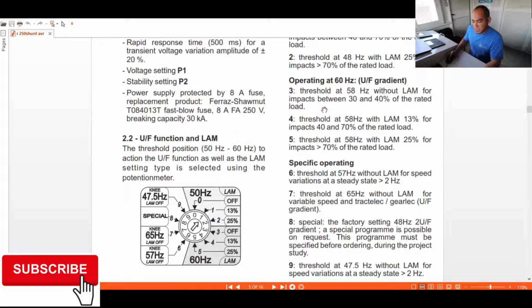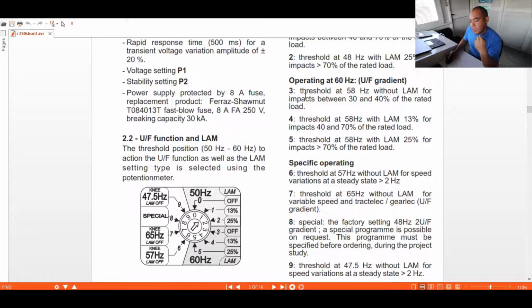Okay, so here is our 60 Hertz under frequency gradient. This is number 3. The first time we were talking about 50, so now we are talking about 60. So number 3, threshold at 58 Hertz without LAM, impact between 30 to 40% of the rated load. This one is without LAM, so you can apply only 30 to 40% rated impact load. Next is the threshold at 58 with the LAM at 13%. The impact load can be applied at 40 to 70% of rated load. Number 5, threshold at 58 Hertz with the LAM at 25%, it can be applied up to 70% rated impact load.